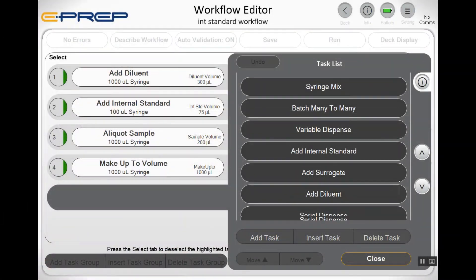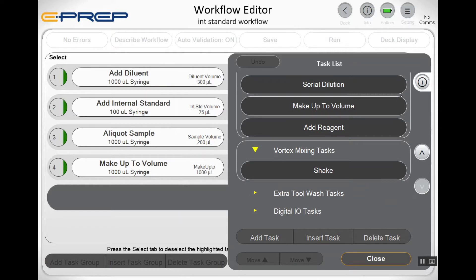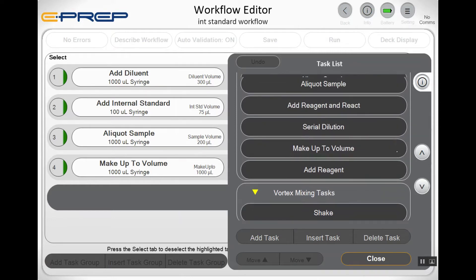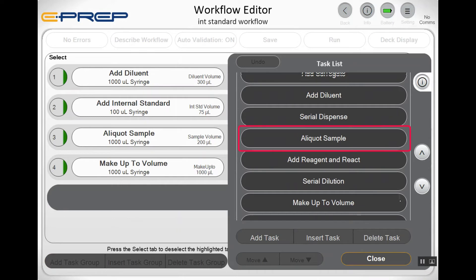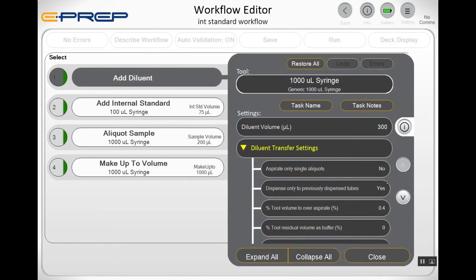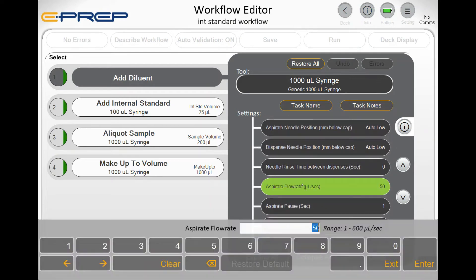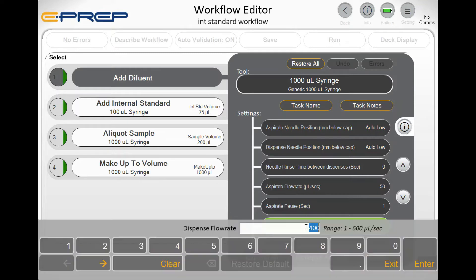The E-PREP software is designed so that a more experienced lab person will easily identify with lab-based steps, such as filtering, sample aliquoting, solid phase extraction cleanup, internal standard addition, and even make up to volume. These are all off-the-shelf tasks which are part of the E-PREP software. Each of these tasks will have parameters associated with them — for example, how fast should the solvent be aspirated and dispensed from the syringe, how hard and how long to shake the vials before they are thoroughly mixed, and so on.